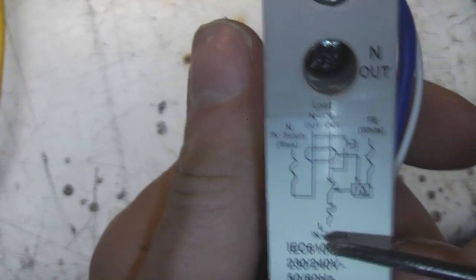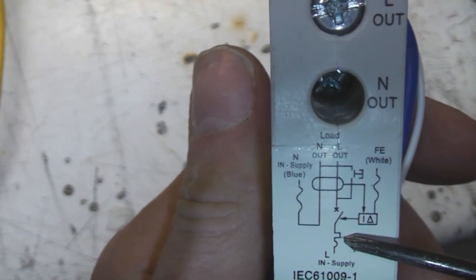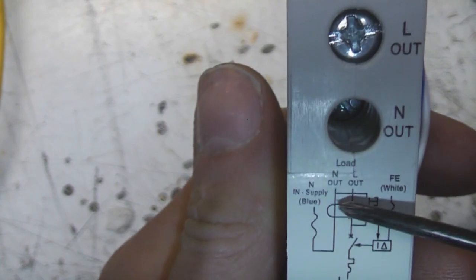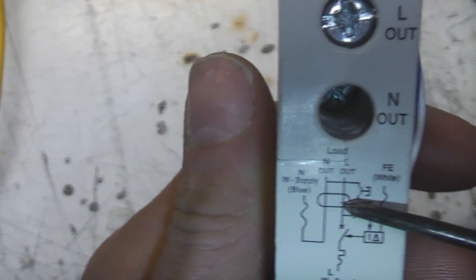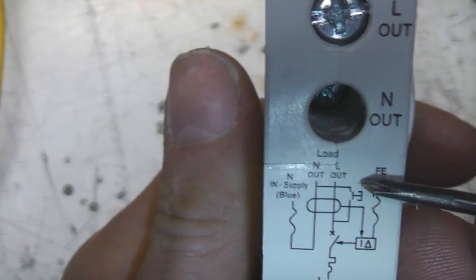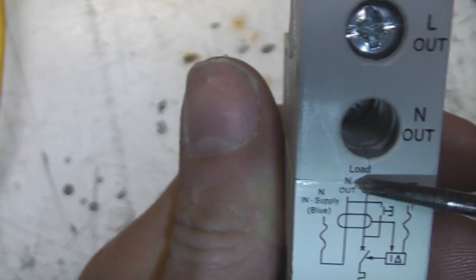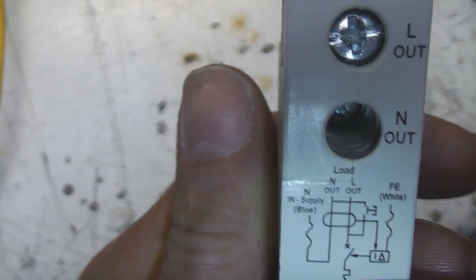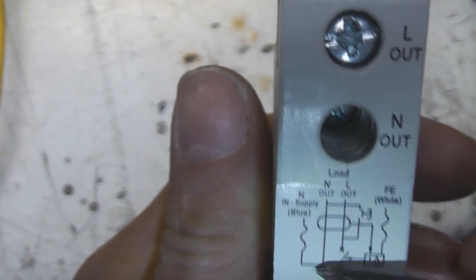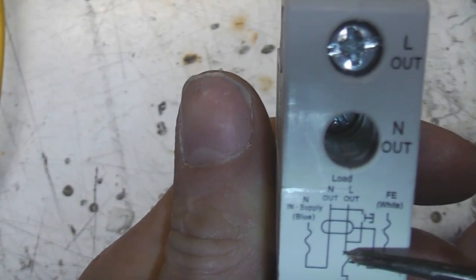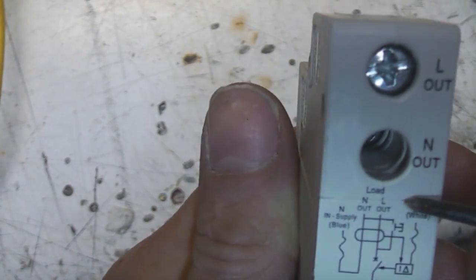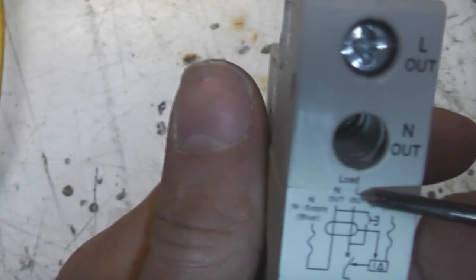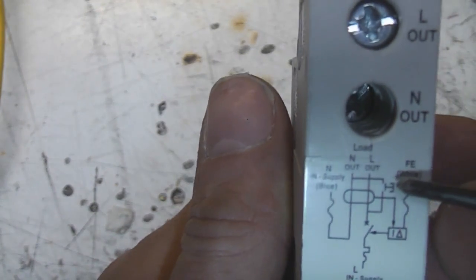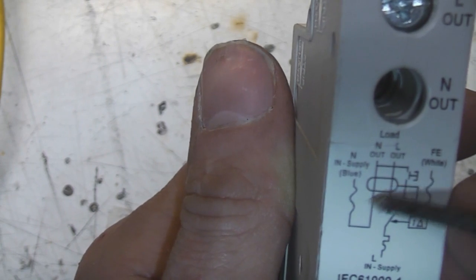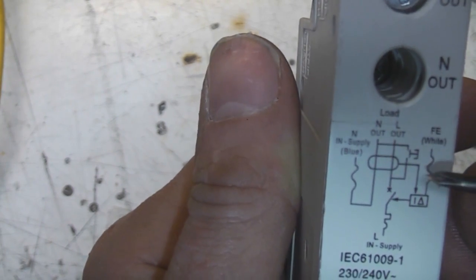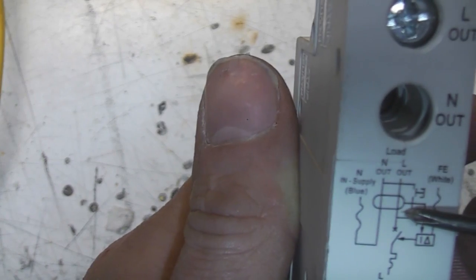Basically, you have your incoming supply. It's got a thermal and magnetic circuit breaker, and it's got this current transformer to measure any imbalance. Normally on a normal circuit, you've got your mains coming in, and it should all go back out the same way it came. If there's an imbalance between the current going one way and the current going the other way, that means it's leaking somewhere, like somebody's touched it or there's water in it or something, which is generally a bad situation. So this current transformer measures that imbalance and then trips out the circuit to ensure safety.